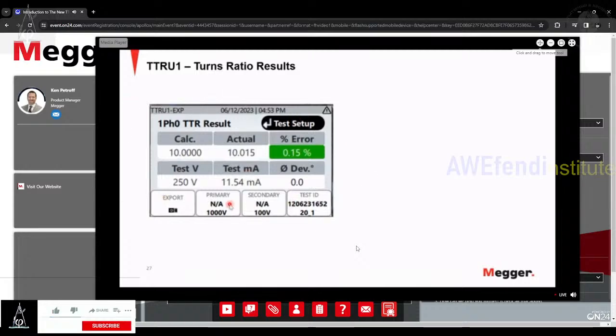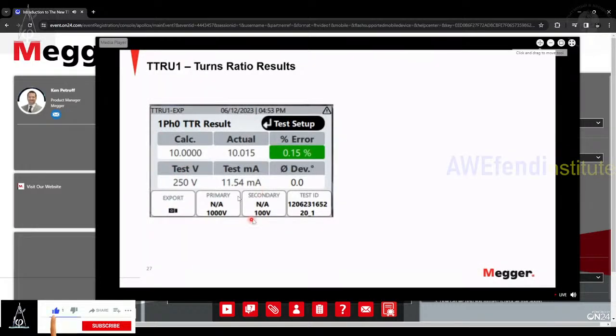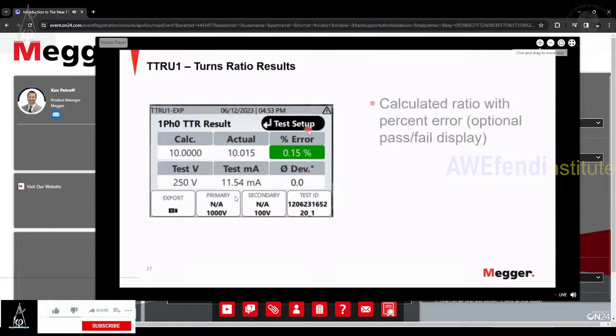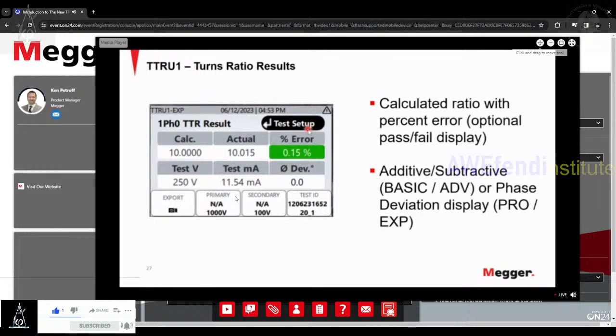Looking at the turns ratio screen, here the customer entered in some information, in this example a primary voltage and a secondary voltage. We provide the calculated ratio based on these values, the actual measured value, and then the percent error. You can also have this percent error display as a pass-fail if you would like, making it even simpler for operators to understand if something is within the limit or not without having to see the percent error. In addition, the TTRU1 will show additive or subtractive based on the transformer vector that you connected to. In the Pro and Expert model, we give you the phase deviation that you're seeing here. Again, it's based on user needs and what is part of your testing program today.